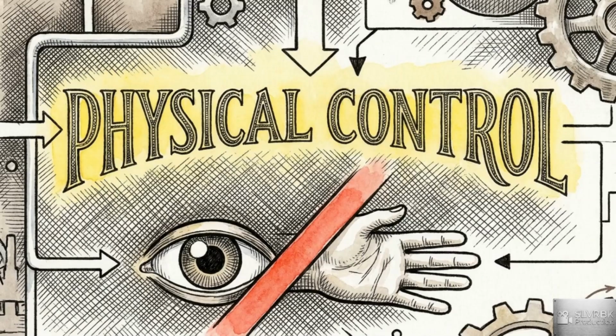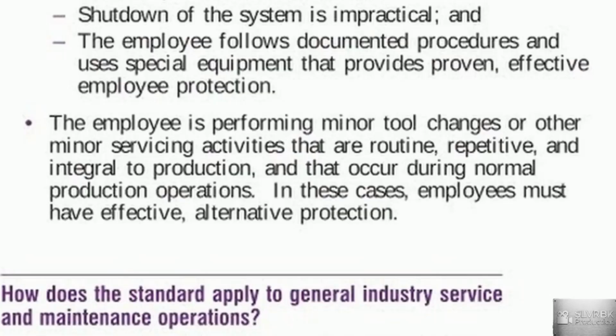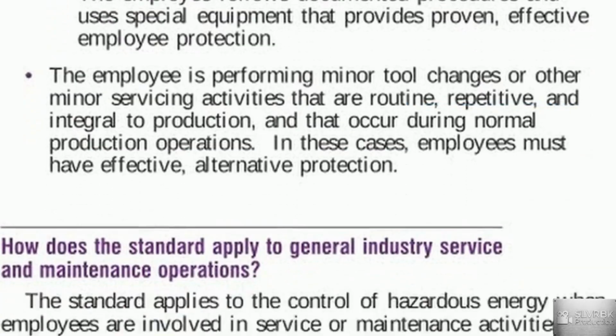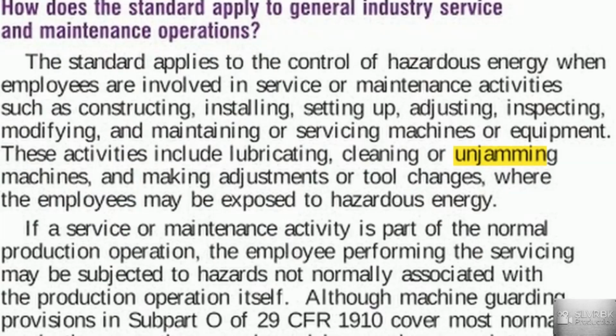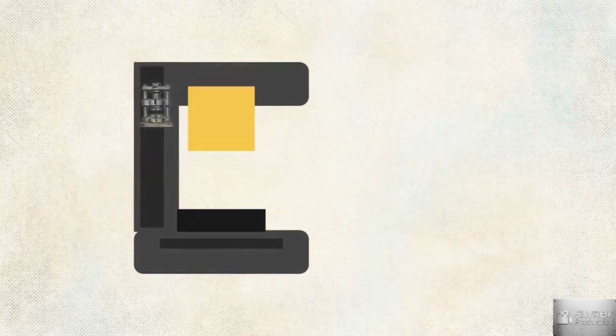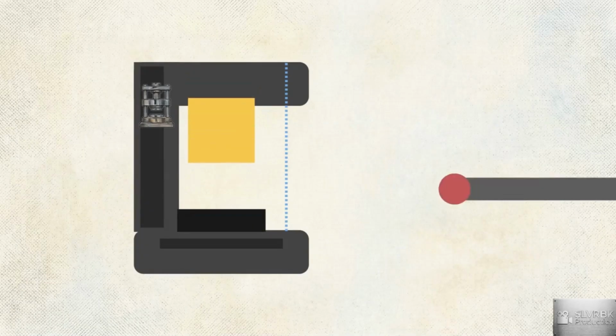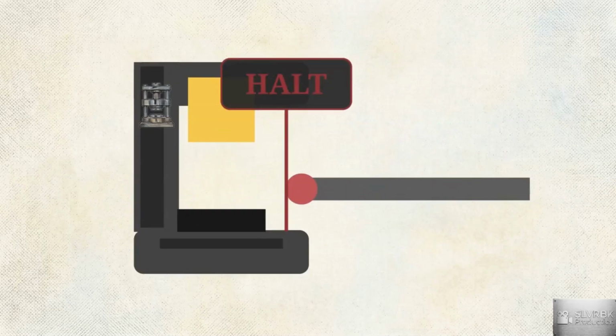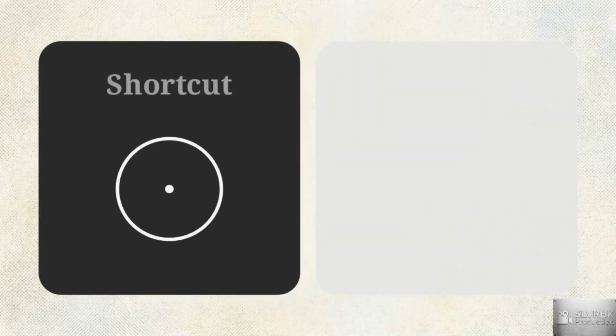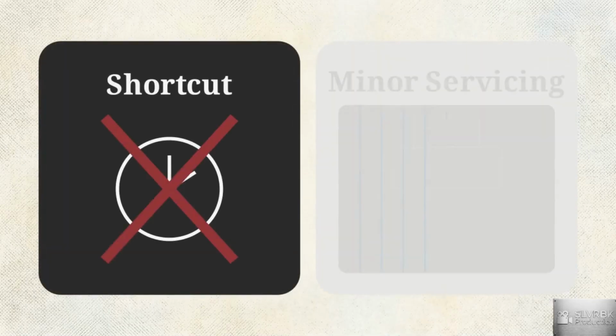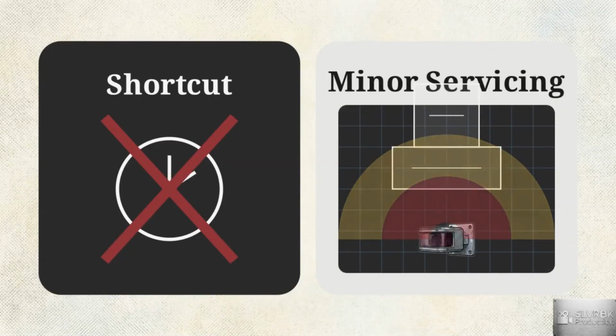The minor servicing exemption allows certain quick tasks without a padlock if they meet 3 rigid criteria. The task must be routine, repetitive, and integral. Clearing a standard material jam qualifies. Fixing a sudden breakdown does not. Even if a task meets those 3 criteria, the worker must still be shielded from hazardous motion. This diagram shows alternative effective protection, like a safety-rated light curtain, that automatically halts the machine's cycle if the boundary is crossed. Stating that a task will only take a second never justifies skipping safety protocols. If a procedure truly qualifies as minor servicing, it requires heavily engineered safeguards to replace the missing padlock.